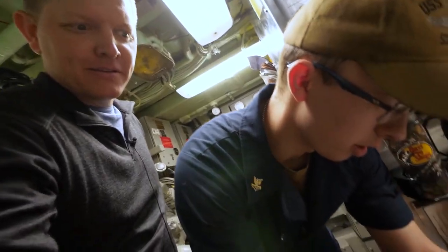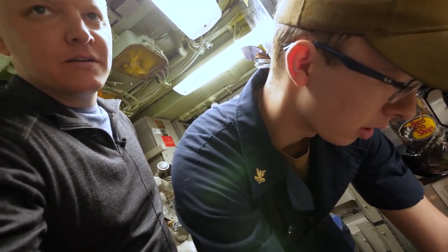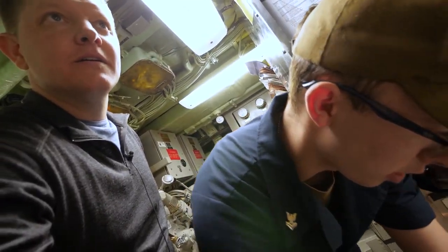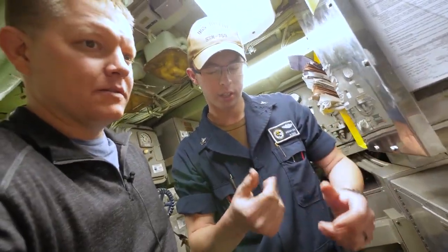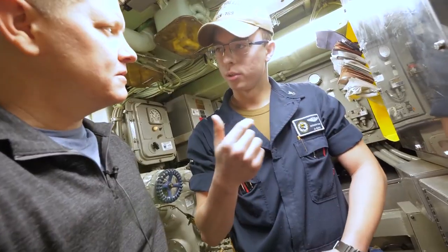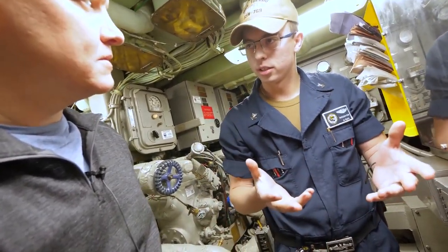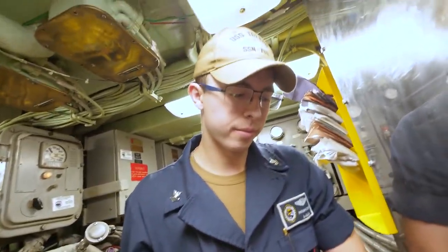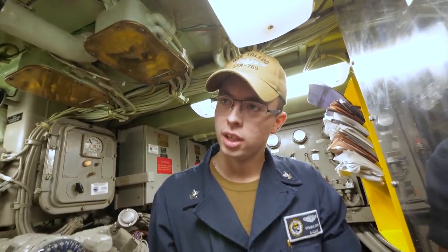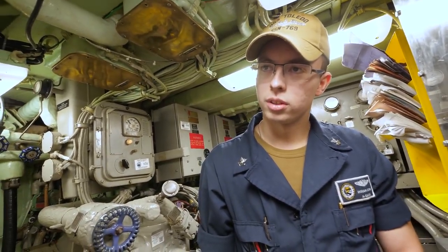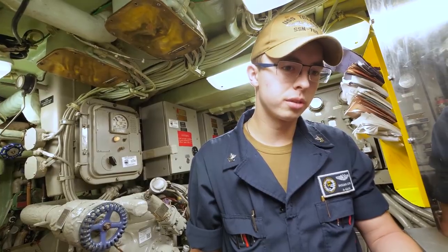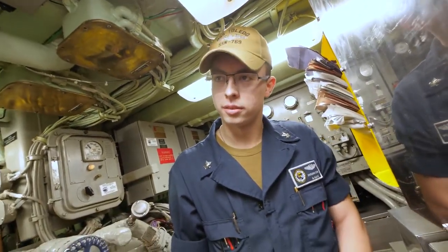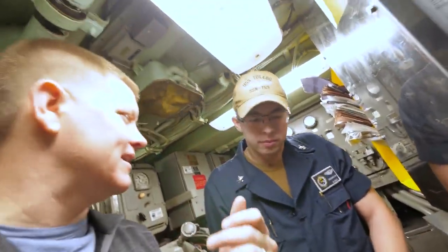We have a Dräger kit. It tests a sample of the air. It's little tubes you break, and you pump air through them, and it'll indicate if there's that type of gas in the air. We also have the PhD6, which tells us the lower explosive limit. So like for hydrogen, for example? Yes. So you have a sniffer that does that.